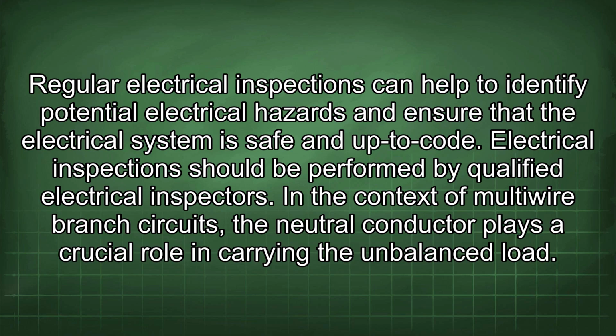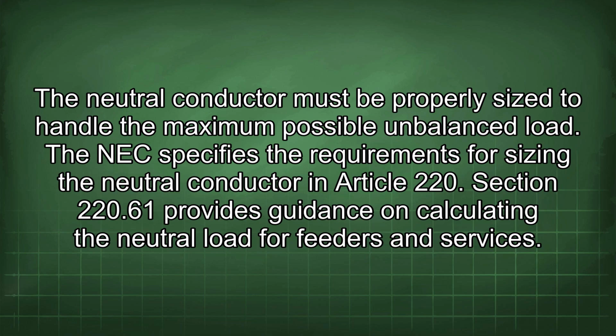In the context of multi-wire branch circuits, the neutral conductor plays a crucial role in carrying the unbalanced load. The neutral conductor must be properly sized to handle the maximum possible unbalanced load. The NEC specifies the requirements for sizing the neutral conductor in Article 220. Section 220.61 provides guidance on calculating the neutral load for feeders and services.